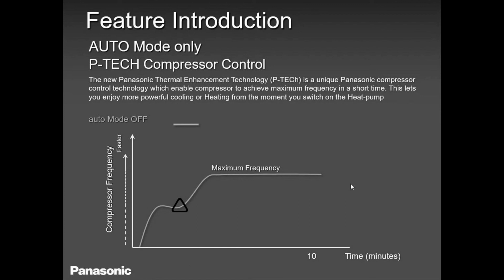Okay. So what I was talking to you about was the 10 minutes. That's the time you can wait if you are doing troubleshooting, guys. Our compressor will take a maximum of 10 minutes to reach its maximum frequency, maximum speed. When you start the unit, it takes about 3 minutes of slow start, and after 3 minutes it will start ramping up. So please don't conclude that the compressor is not ramping up in those first 3 minutes. Give it some time. Look at your running amp. It will probably start at 1, 2, 3, 4, and it will keep going higher and higher.